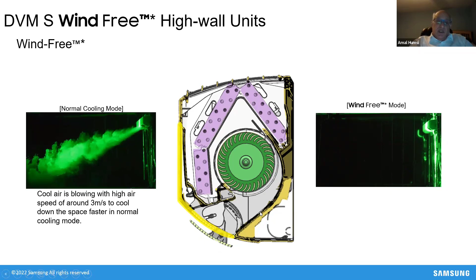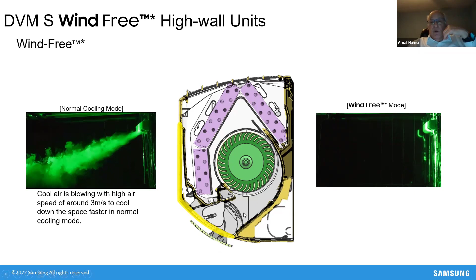And the concept there is simple. So if you have a high wall system, when you start the system, basically the unit will blow the air like a typical unit until it reaches the set point. Once you reach the set point, the louver closes, and then the air is discharged around the front of the cover. And what Samsung has, on this particular unit, a high wall, we have 21,000 micro holes where the air diffuses through those holes. And when it discharges from those holes, then the velocity of the air that is leaving the unit is very low velocity, less than 0.15 meters per second, which per ASHRAE is standstill. So you're cooling the room, you are doing it at very low RPMs, you're saving energy, and you are giving even temperature everywhere in the space.